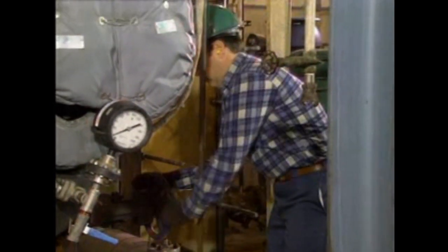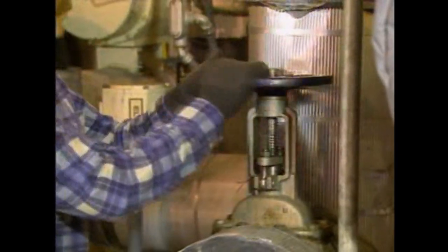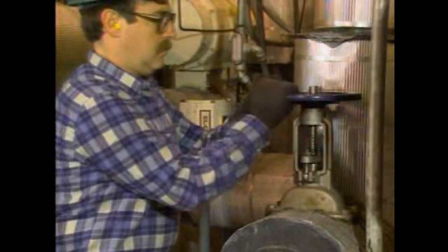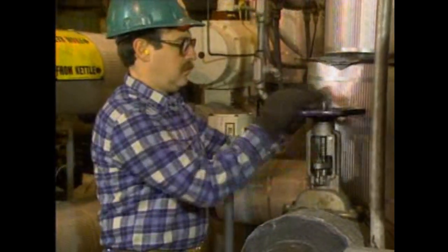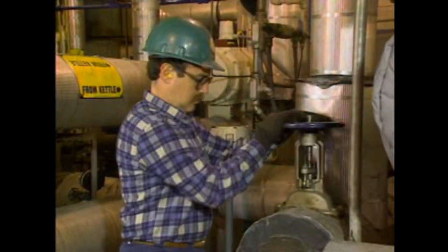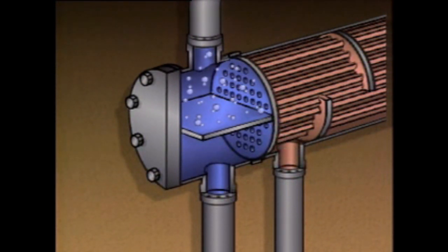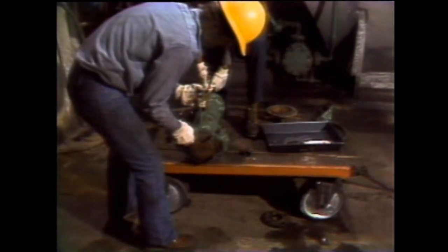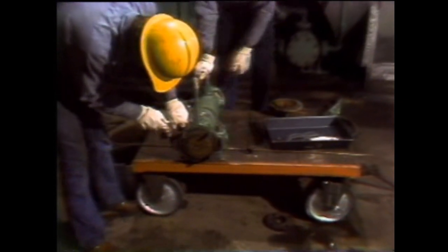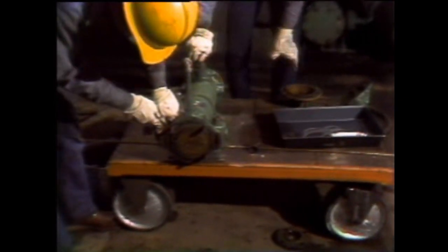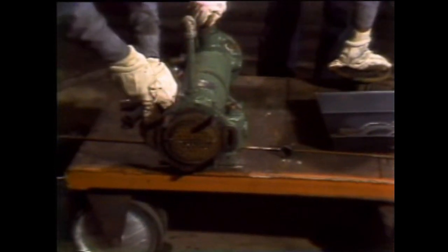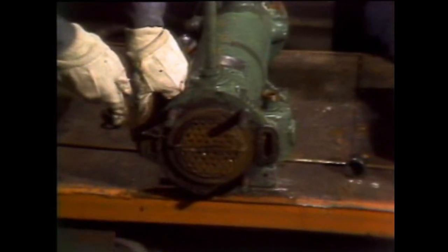There are many ways that air or other gases can get trapped inside a heat exchanger. For example, this can happen during the startup of the unit — if the venting is not complete, gases will remain inside. Another source of gases is the process itself; in some situations, the process can produce vapor bubbles that collect inside the unit as process fluid passes through. When maintenance is performed on process equipment, air may be trapped in the piping or shell as the equipment is put back together, and when the equipment is restarted, the air can make its way to the heat exchanger and become trapped inside.